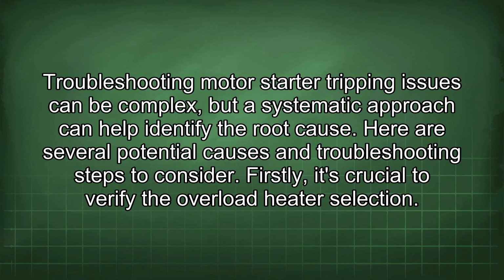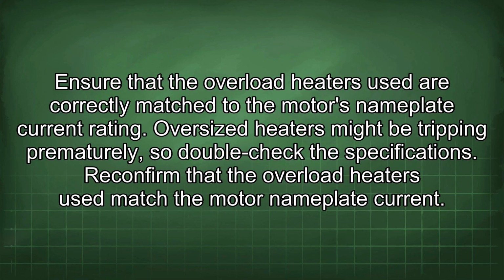Troubleshooting motor starter tripping issues can be complex, but a systematic approach can help identify the root cause. Here are several potential causes and troubleshooting steps to consider. Firstly, it's crucial to verify the overload heater selection. Ensure that the overload heaters used are correctly matched to the motor's nameplate current rating.